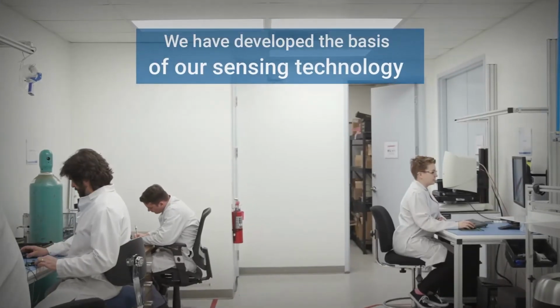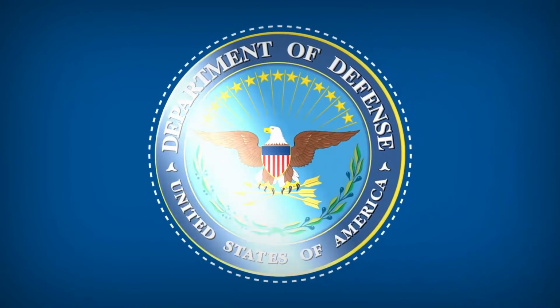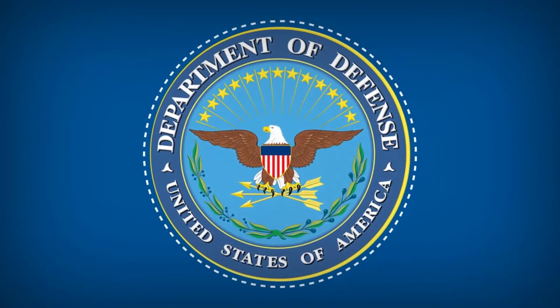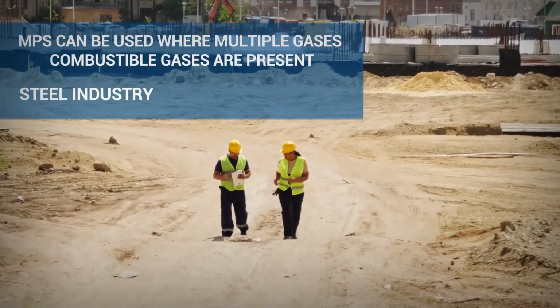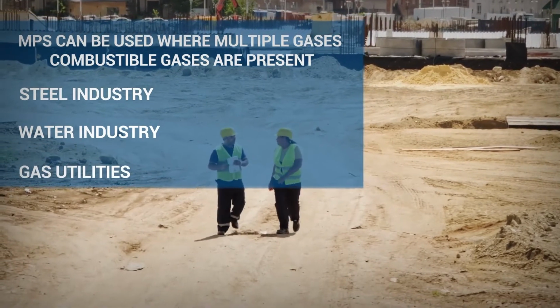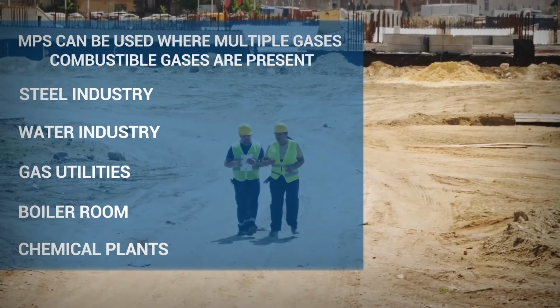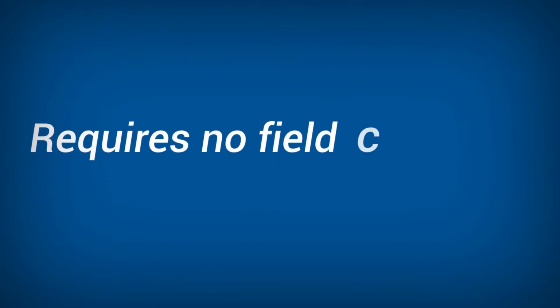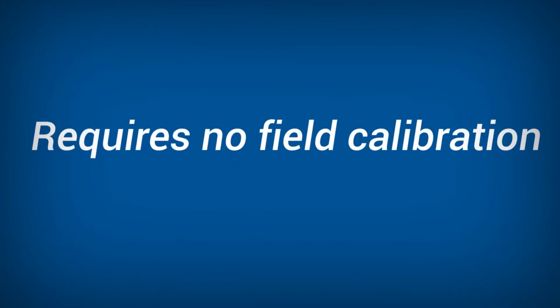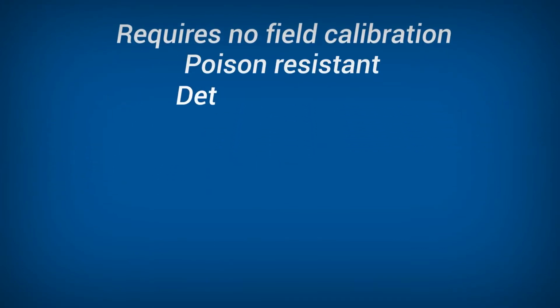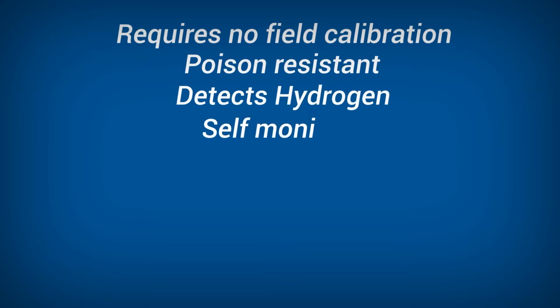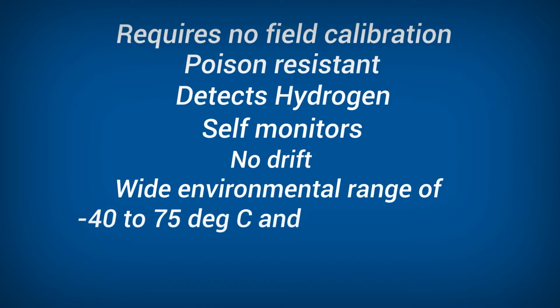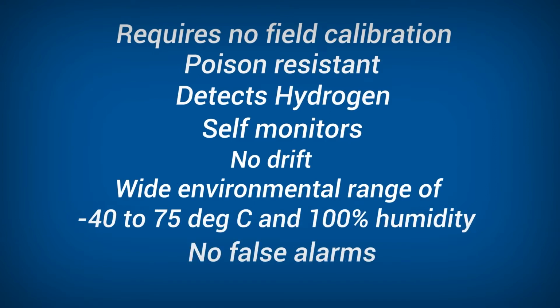We have developed the basis of our sensing technology with the U.S. Department of Defense in the most challenging gas detection applications and are now available for the safety and control systems market. The MPS gas sensor requires no field calibration, is poison resistant, detects hydrogen, self-monitors, has no drift, and operates in up to 100% humidity, making false alarms a thing of the past.